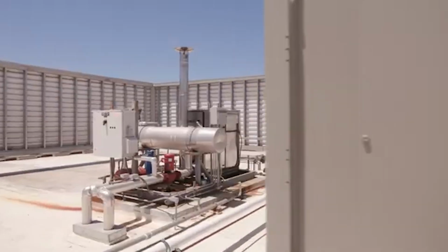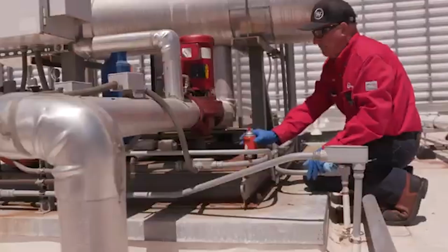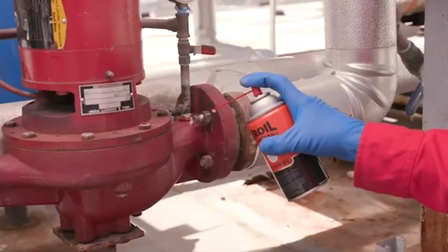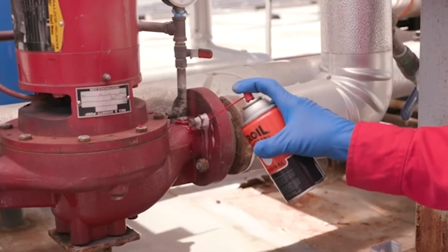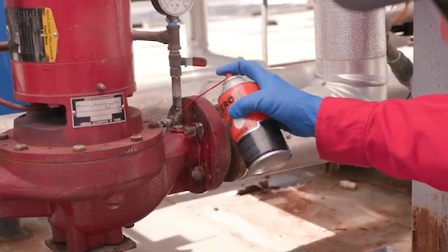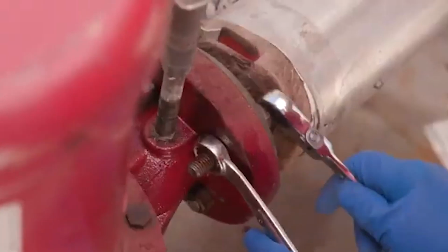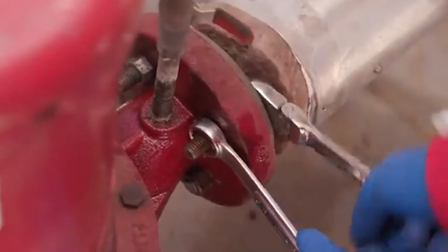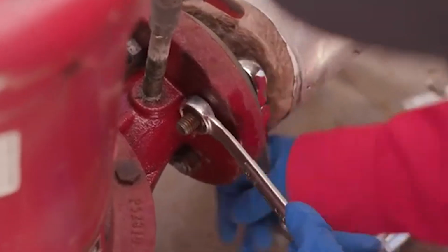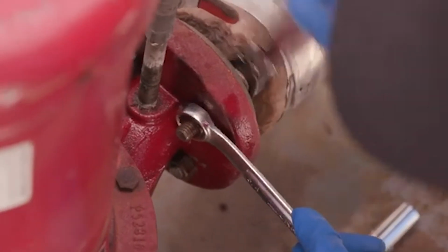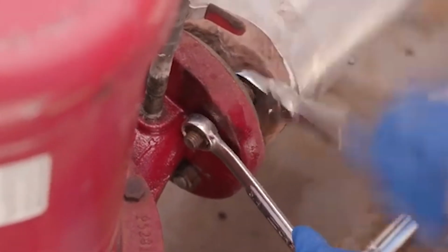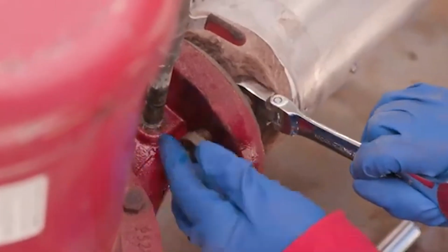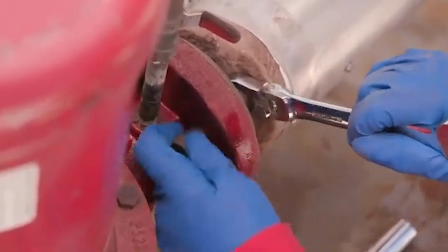Some of these repairs were just general maintenance the guys were taking care of. One was a boiler pump we needed to replace and upsize - it didn't have enough capacity for the space, so we had to remove that pump from the rooftop and put a new, larger one in place. To do that, we had to break loose the base it was mounted on and reconfigure some things. That thing had been sitting there for a decade since we installed it, so it was really hard to break loose, and we needed a penetrant to help us break those bolts loose.